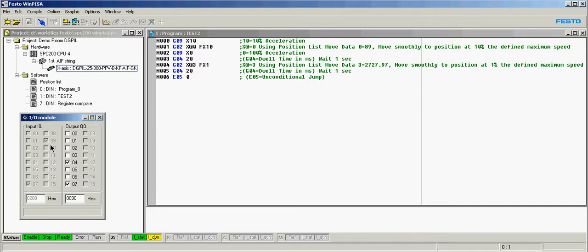Before I do that, I just want to show you the status of the I.O. You'll notice that we have input 7, which is the stop. It has to be high. Down here, you get the green, and input 9, which is the enable, has to be on. If it's not on, then you lose the ready. If the stop's off, you can't move the axis.